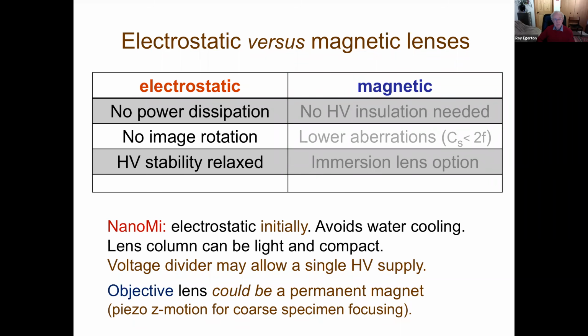Electrostatic lenses don't rotate the image. That's not really a major advantage. But another advantage is that the stability of the power supply can be less with electrostatic lenses. The reason for that is that if you use the same power supply to accelerate the electrons and to drive the lenses, if the voltage increases, the electrons are traveling faster, and that would make the focusing less strong. But if you have the voltage applied also to the lenses, the focusing is compensated. So you have a system which is relatively insensitive, to first order, to the voltage of the lenses and the accelerating voltage. And so we have in mind to devise a voltage divider system that would allow a single power supply, which would reduce the cost and maybe help with the stability of the instrument.